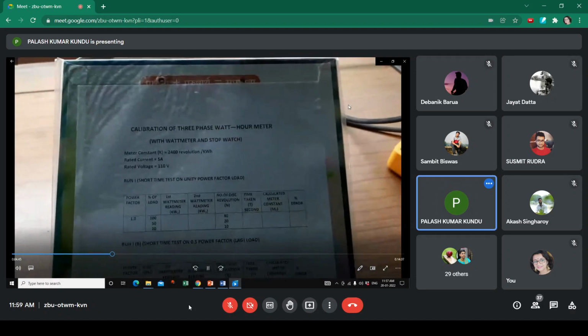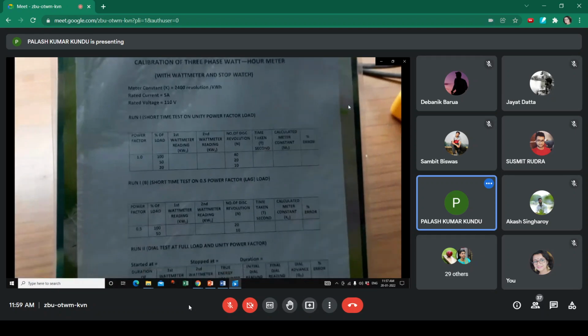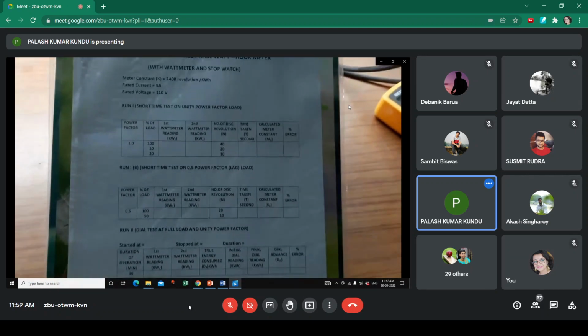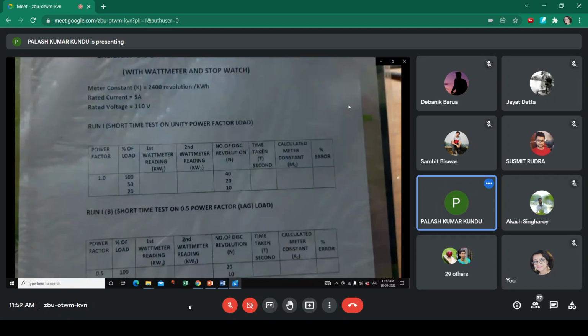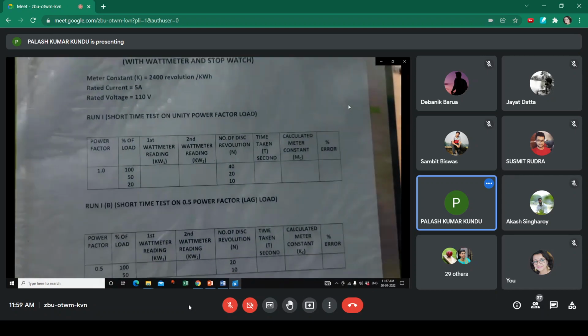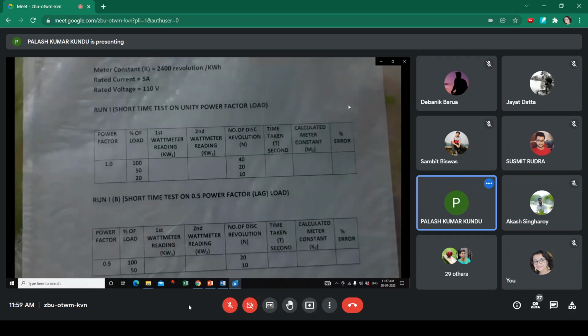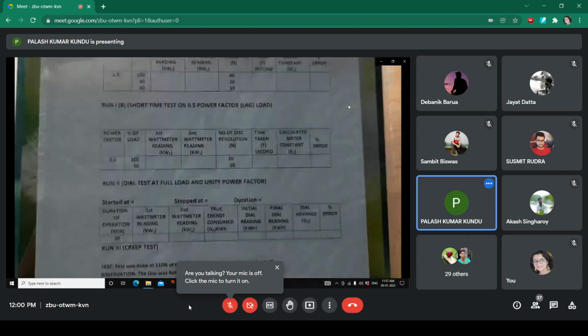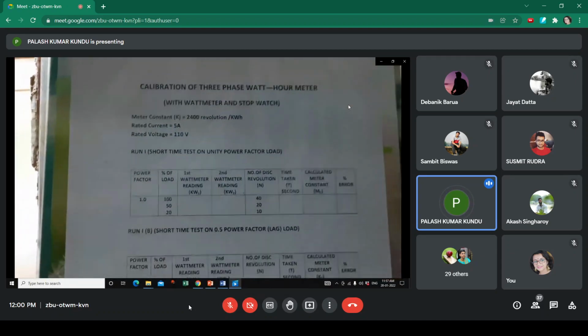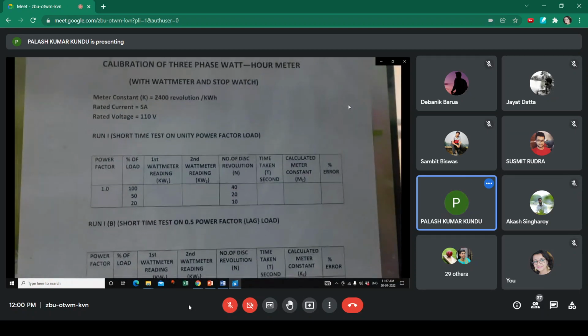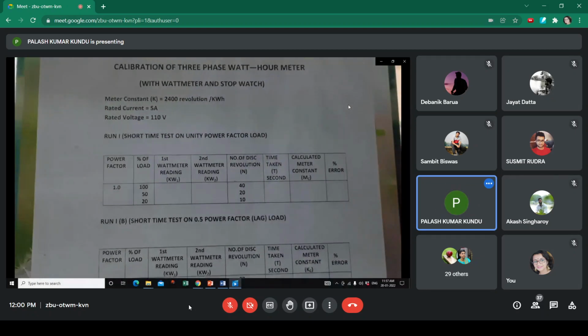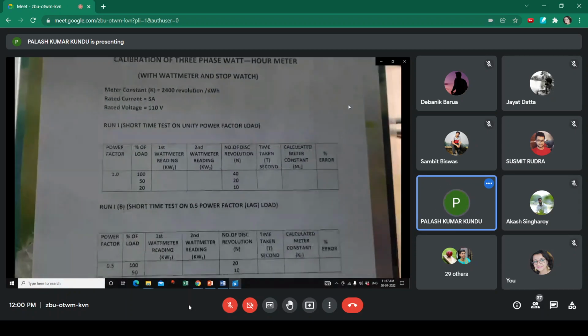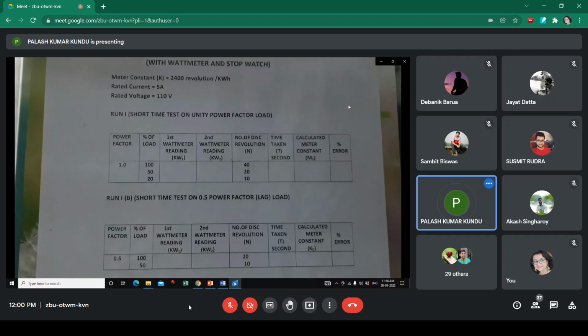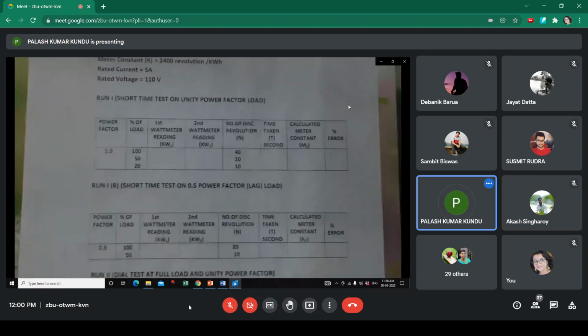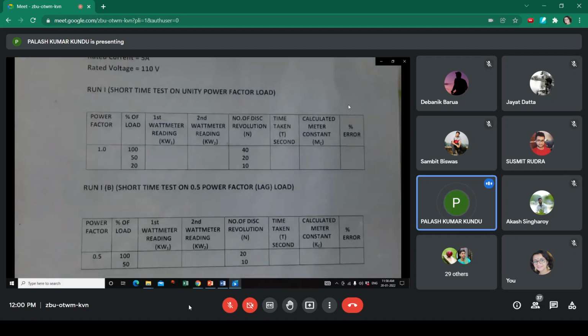Now we are going to the experimental part. So we have a total of three runs. Run one, short time test at unity power factor. In this test, we will take the power factor as 1, that means unity power factor. At unity power factor, we change the load: the first reading will be at 100%, then 50%, then 20%. Accordingly, we will check the total revolution time. At 100% load, we will take the time for 40 revolutions of the disk. At 50% load, we will take the time for 20 revolutions of the disk, and again at 20% load, we will take the time for 10 revolutions of the disk.